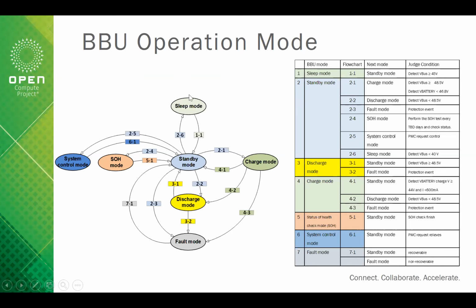Once we install the BBU into the 48 volt BBU shelf and connect it with the 48 volt, the BBU will go into the standby mode. Once this voltage is higher than 48.5 volt, it allows the BBU to recharge. Once we detect the BBU SOC level is lower than our setting number, we go to the charge. And once we get the full charge, it will go back to the standby mode.